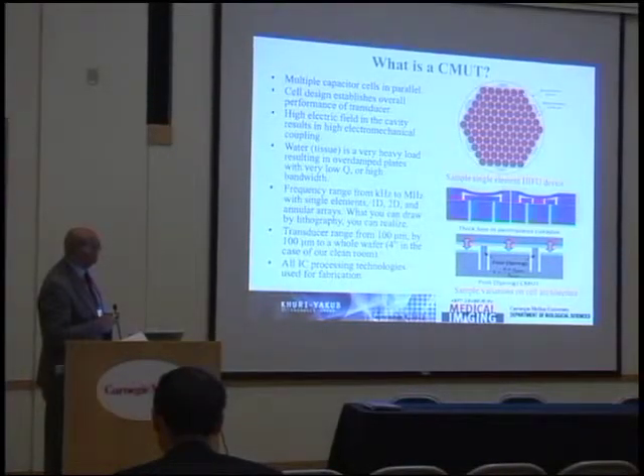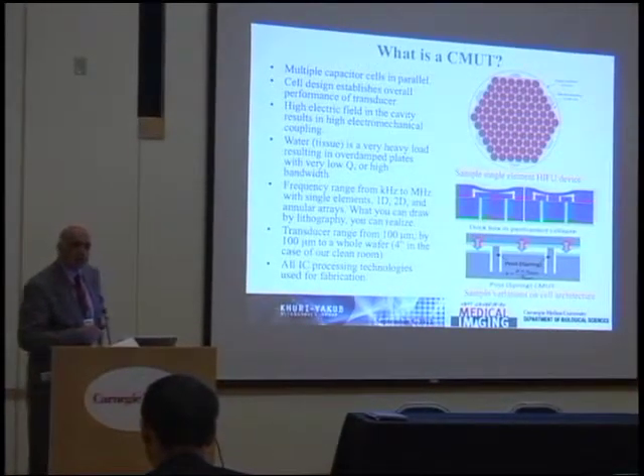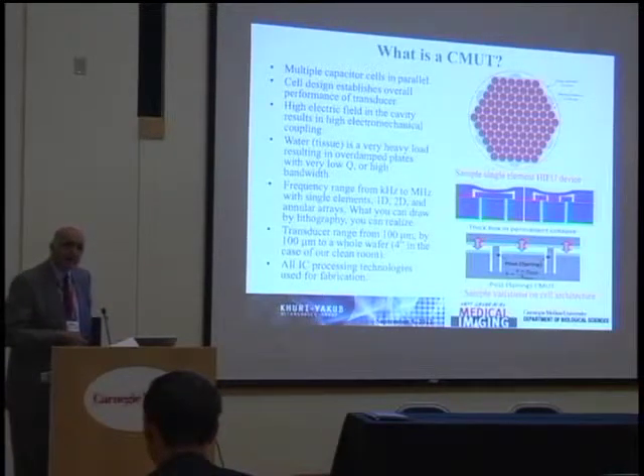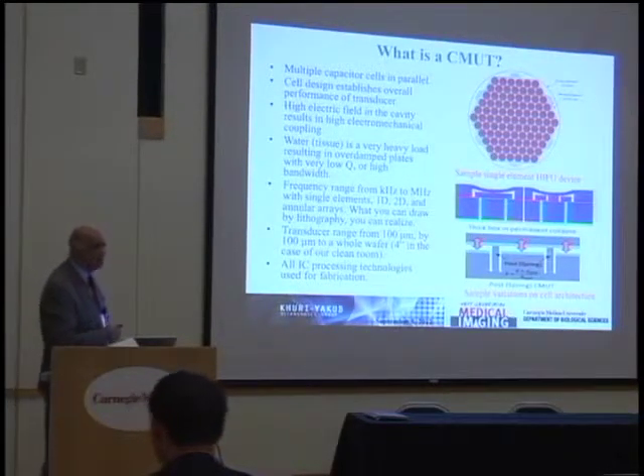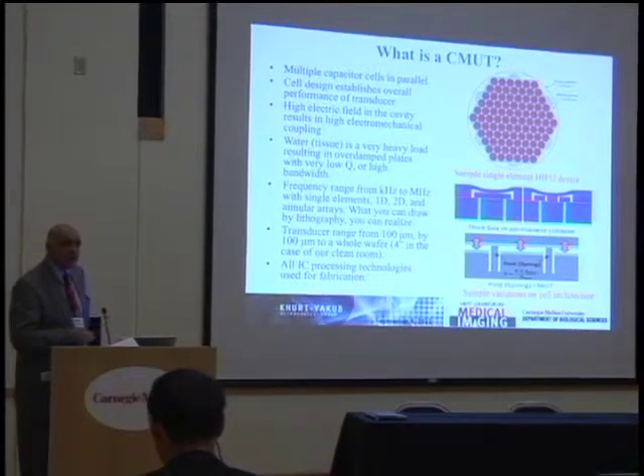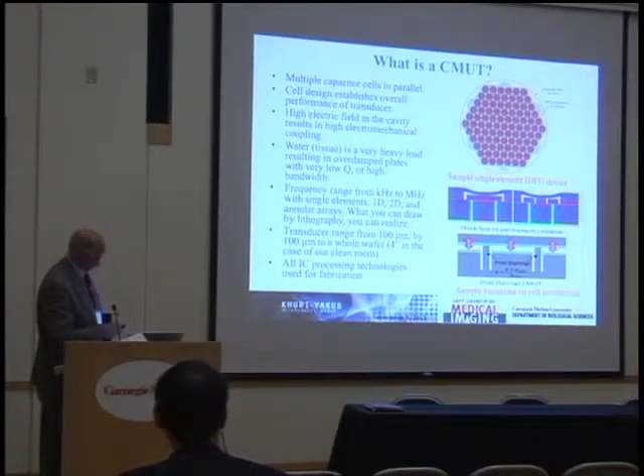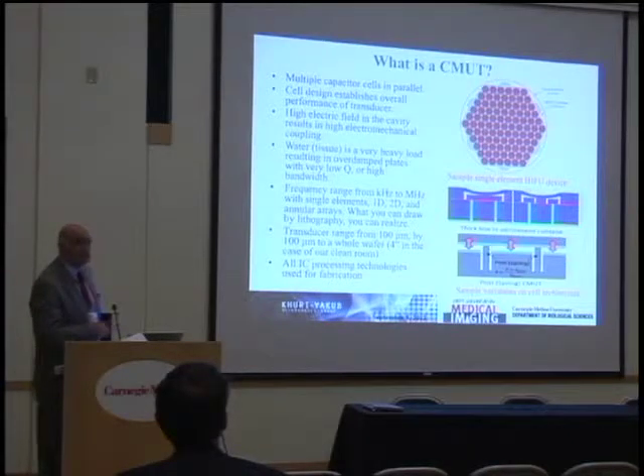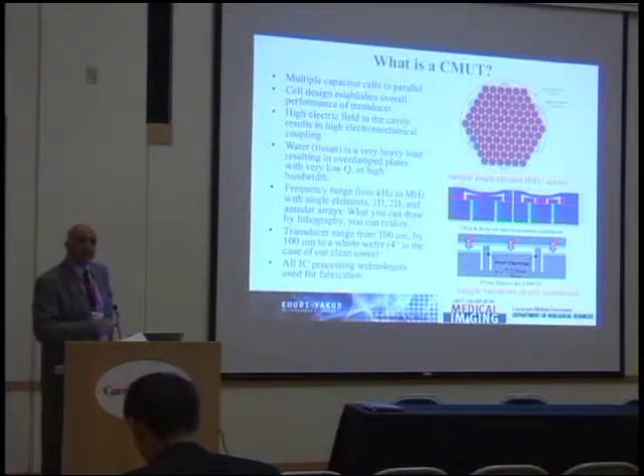So what's a CMUT? Well, it's a capacitive ultrasonic transducer, and it's typically made looking something like this. You have a lot of cells. Each one of these circles is a cell, and each one is an individual capacitor. It's a plate that is vibrating over a substrate with a gap in between, and the characteristics of the cell basically dominate the total performance of the transducer. A transducer or an element is made by putting a number of these in parallel.